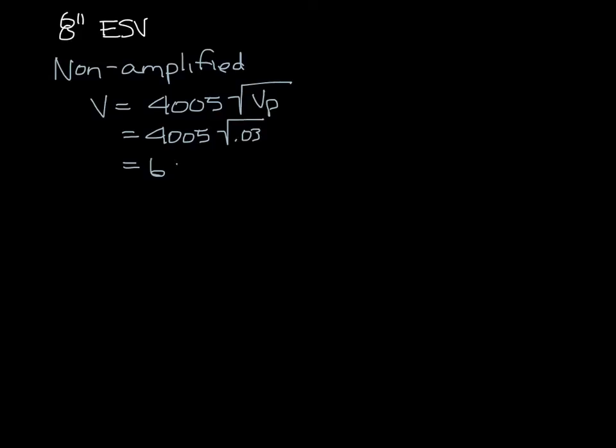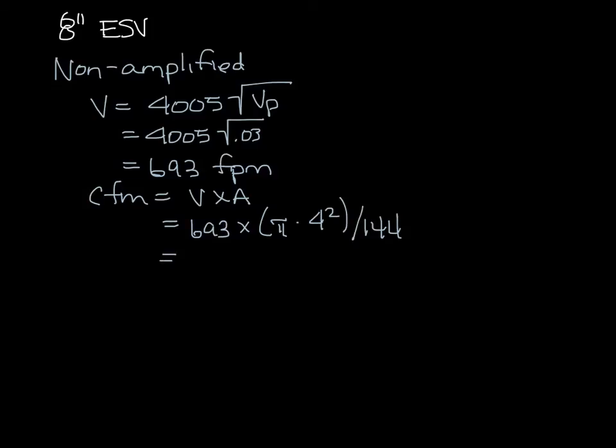And if we convert that to CFM, CFM equals velocity times area. So that's 693 times the area of the 8-inch ESV divided by 144 to get it into feet. And that's 693 times 0.349 equals 242 CFM.